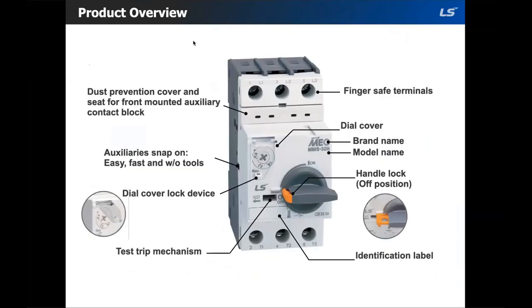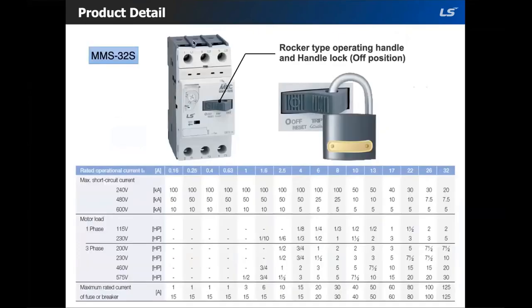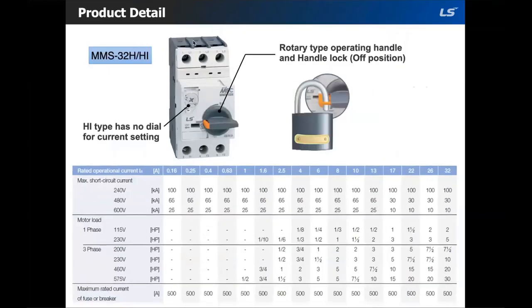So here is the front view of the MMS32H. The MMS32S comes with the rocker type operating handle, and it can be locked in the off position. As you saw, MMS32H/HI come with the rotary type operating handle, and it can also be locked in the off position. The difference between the S model and the H model is the breaking capacity, also known as the short circuit rating. So if you look at the kA rating on these, you would see that the H model has a significantly higher kA rating compared to the S model.